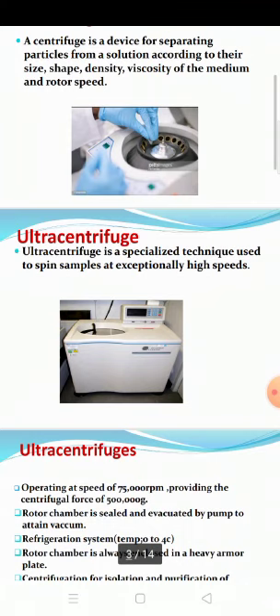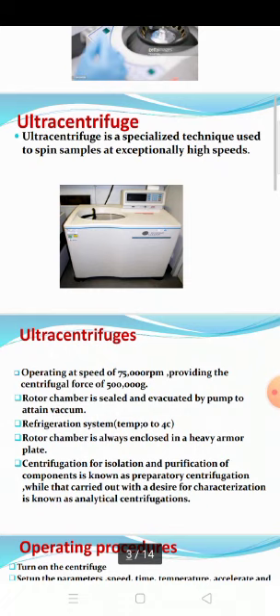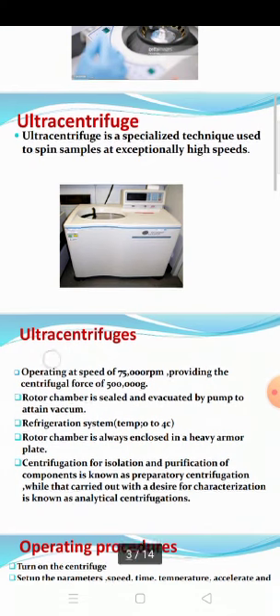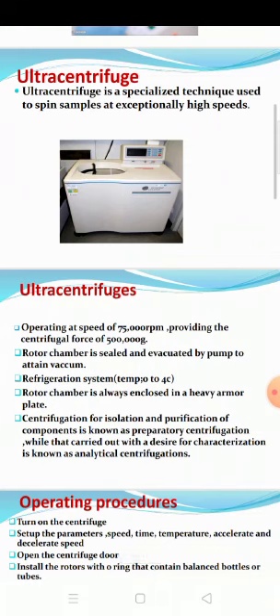Number two, ultracentrifuge. What is an ultracentrifuge? Ultracentrifuge is a specialized technique used to spin samples at exceptionally high speeds. The separation of mixtures, liquids, sediments, suspended solids, particles, and the separation of blood is also done by the ultracentrifuge machine. Ultracentrifuges operate at a speed of 75,000 rpm, providing a centrifugal force of 500,000 g. The rotor chamber is sealed and evacuated by a pump to attain vacuum. A refrigeration system keeps the required temperature of 0 to 4 degrees C. The rotor chamber is always enclosed in a heavy armor plate.